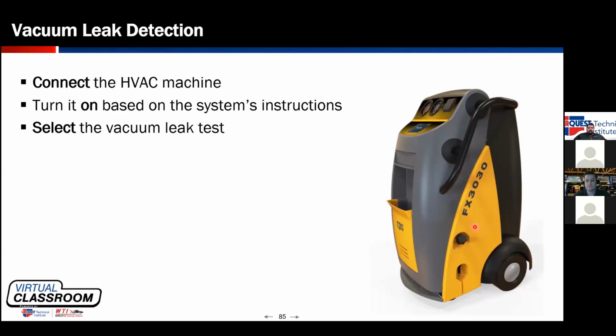We're going to do vacuum leak detection. The downside to vacuum leak detection is it can be hard to physically find where the leak is. It's a great idea to do the vacuum decay leak test to see if you have a leak, but you will probably have to go to another method to pinpoint what the leak is. Most AC machines will do a vacuum decay leak test. Once you pull the system into a vacuum, you'll do the leak test and let the machine monitor it.